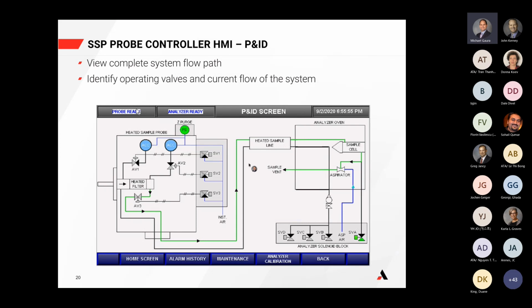And again, Rod mentioned this earlier, our instrument air is filling up these two accumulators and building up pressure, typically around 100 psig is what these are being built up to. And they're storing that pressure in anticipation of doing the blowback. So if you can just do a mental snapshot of what we're seeing here, everything's good to go, and we've got sample running through here, and the actual blowback assemblies are both turned off. So these sample valves are not energized, so we don't have any of that instrument air coming through.